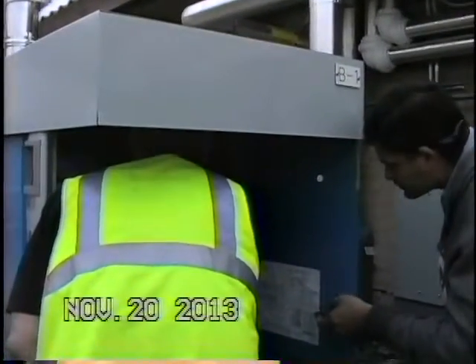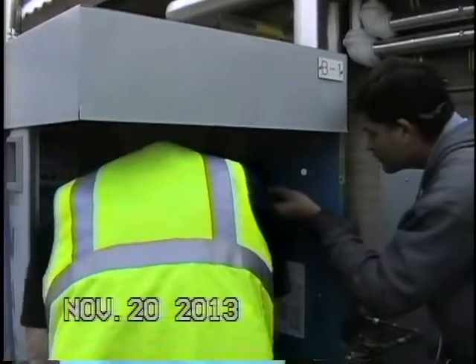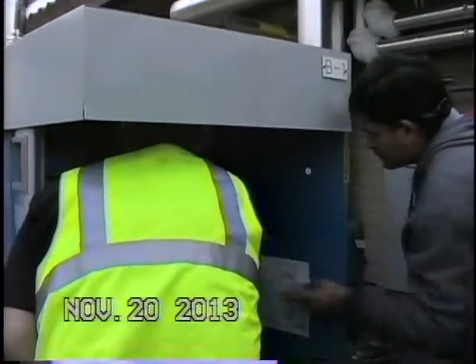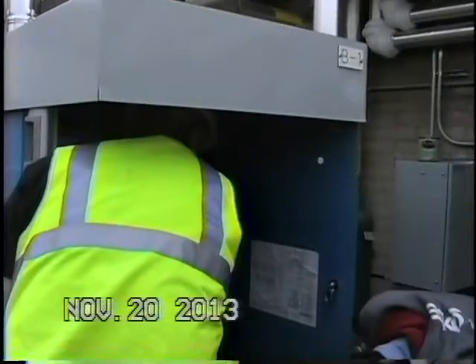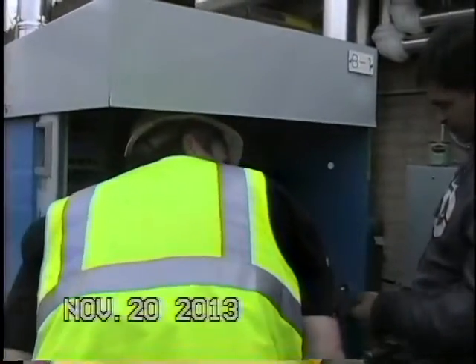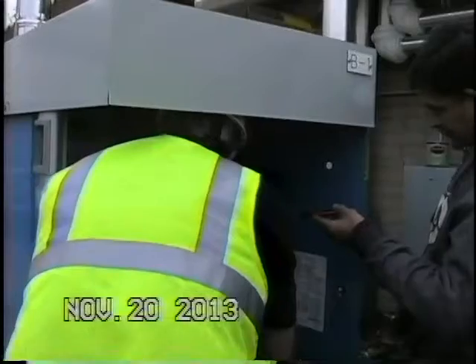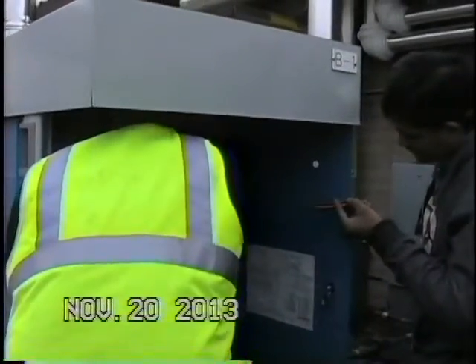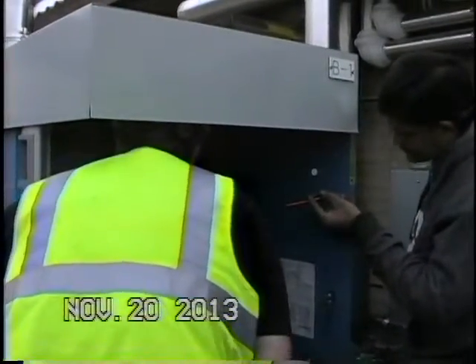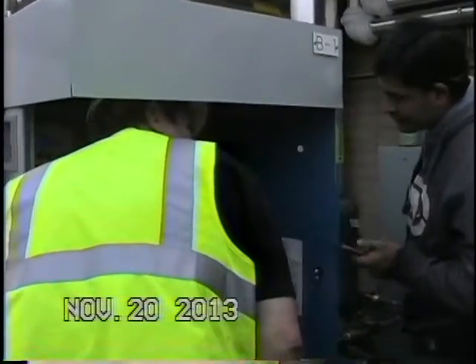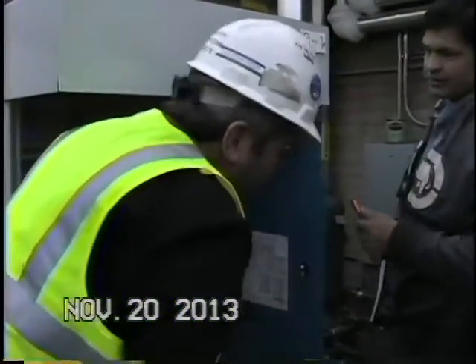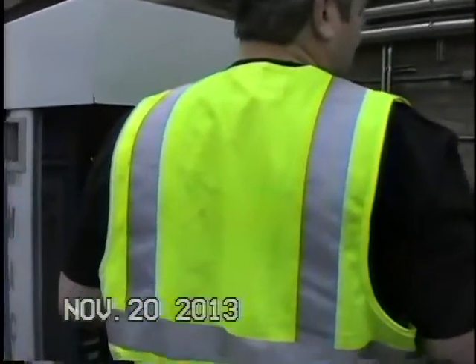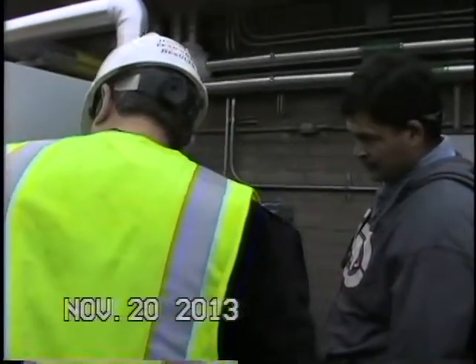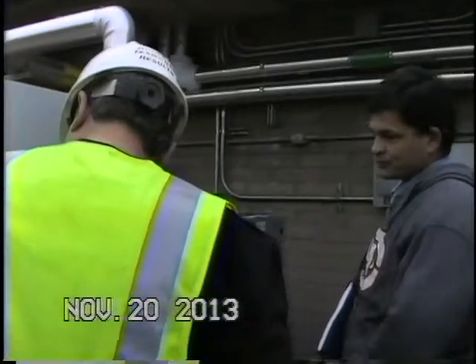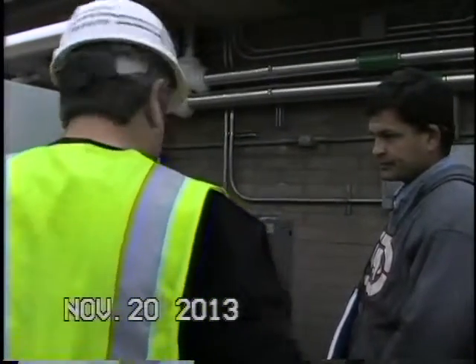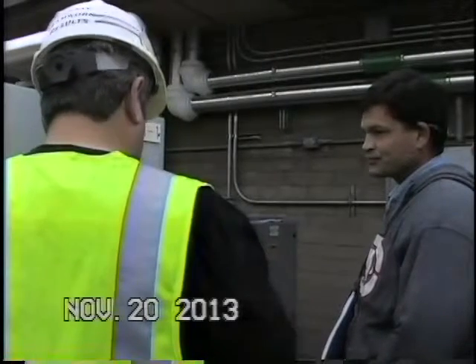This is the gas valve right here, and then the air comes in and it mixes. And then say it pulls it this way. See that's open. It pulls. Yeah, it mixes. So gas comes in this way, that comes in that way. And then it varies the amount of gas? Yeah, depending on how much air. How much demand you have? The gas follows the air.